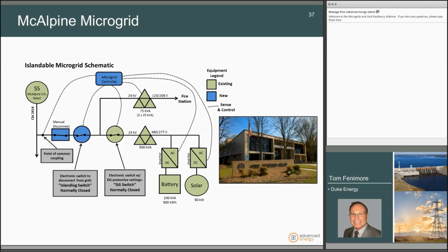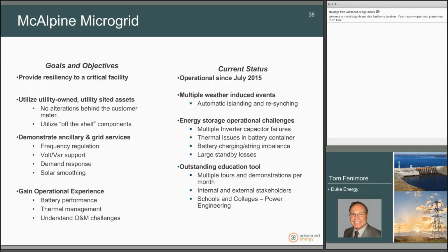Looking at this schematic, you can see we have a 200 kW battery and a 50 kW solar field connected together to feed the fire station through their existing service, so the customer doesn't have to make any changes to their wiring.